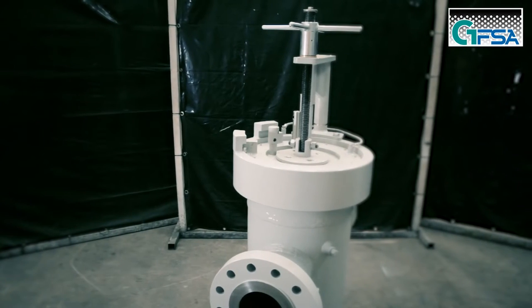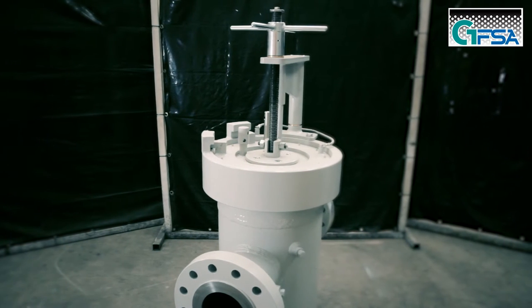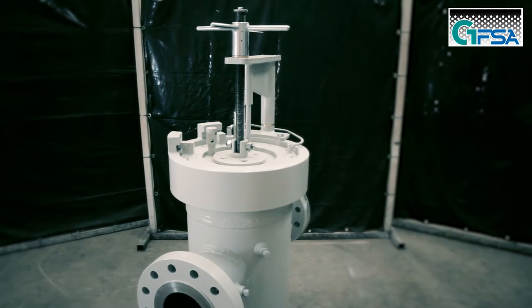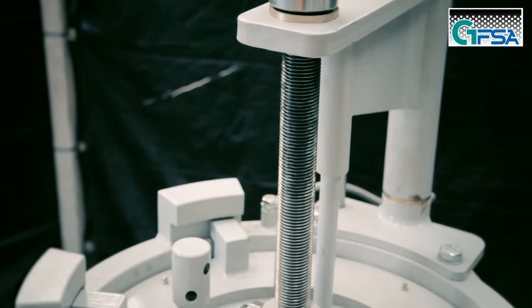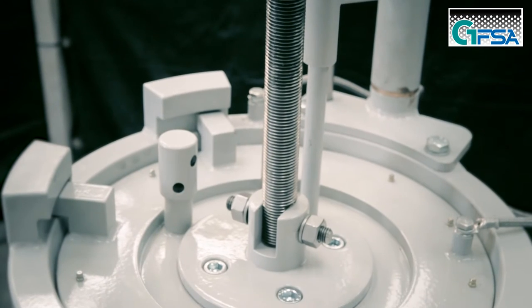Before attempting to open any closure door, it is essential that the vessel and adjoining process lines are depressurized, and that the vessel and pipeline are drained of processed gas or liquid and purged if necessary.